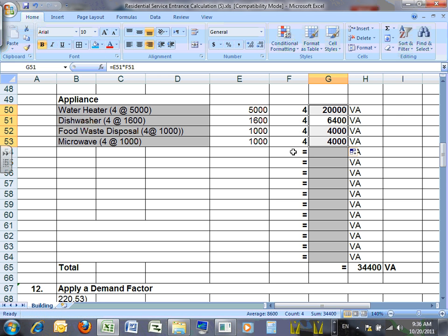Shouldn't change the math. Okay, so what I did, when I'm doing one apartment now, if I want to go now for water heater, one apartment, all I have to do is just put 1 here, and guess what? It calculates it for that particular apartment. So I have 4 here for this. You can do it any way, shape, or form. That's a nicer way, where you have the equipment, volt amp, how many equipments do you have, and their total.